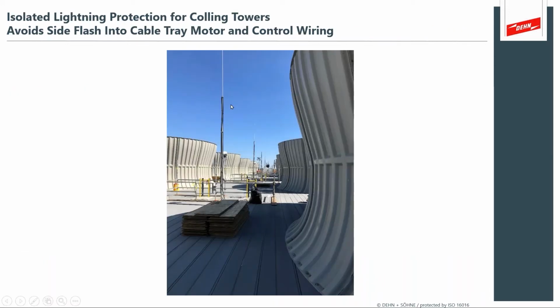This is what that might look like on the deck of that cooling tower. And what's very nice about this photograph is that you can see it's a clean application. We're not applying the air terminals onto the plastic cowling of the structure. We're applying the air terminals onto the light poles that are already there on the site. And we're using isolated air terminals, down conductor and air termination system, so that we avoid side flash into the cable tray and motor control wiring. Because you recall that the cooling provided by this cooling tower is going to be directly proportional to the power generation at the plant.